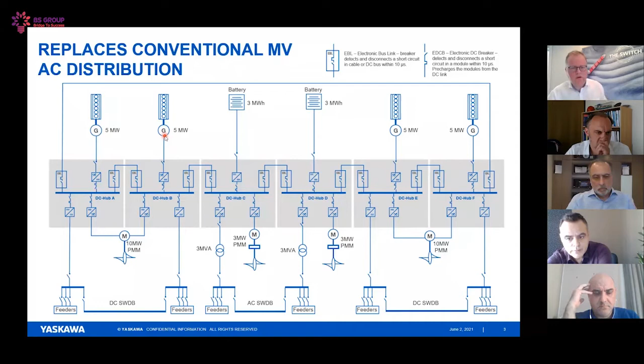When we did that test, we connected the breaker to the cable, closed with the short circuit, closed the breaker, and we could see that these two disconnected while the rest of the machine continued to work - with absolutely no oscillations, not on the feeder side or the generator side. Everything was smooth running because this is so fast.